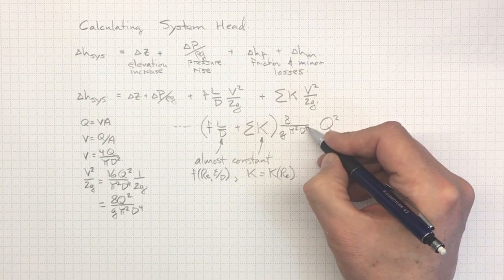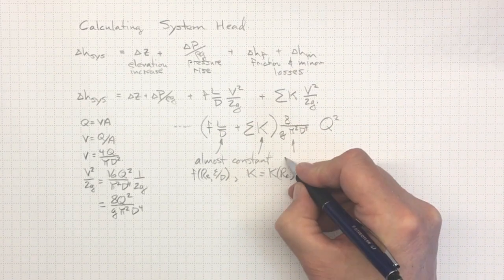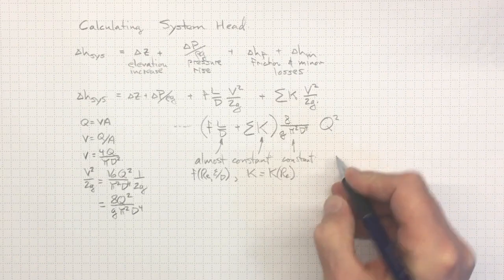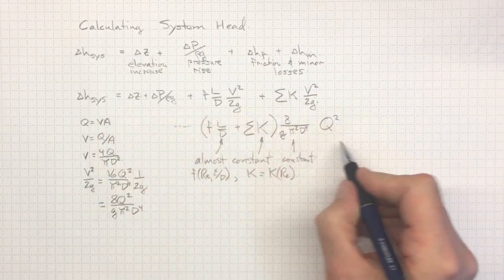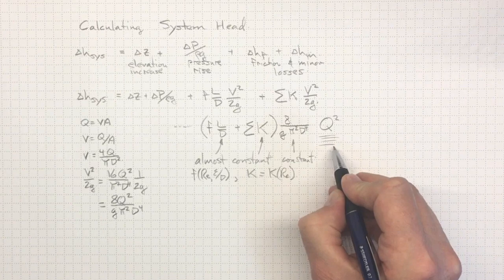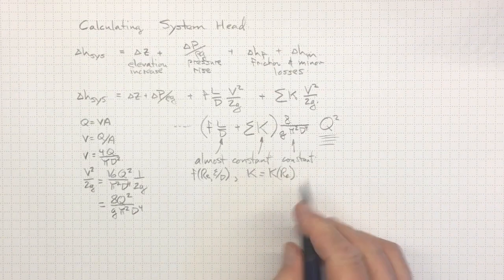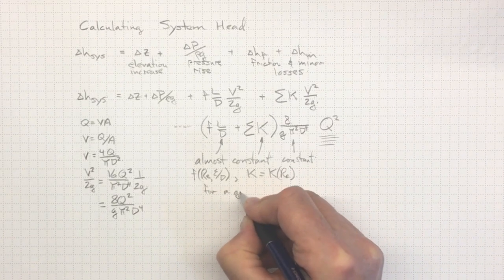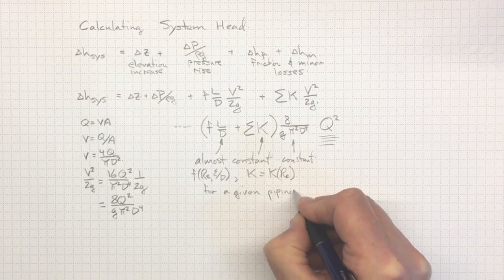And of course, 8G pi squared and D to the fourth, those are just constants. So we'll see that these losses are depending primarily on the flow rate squared. Now these are constants, at least for a given piping system.